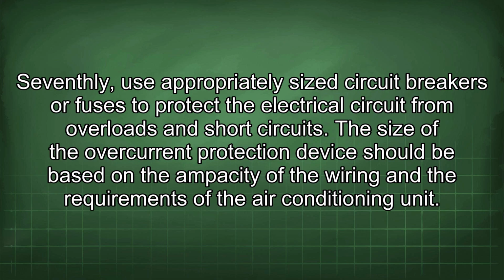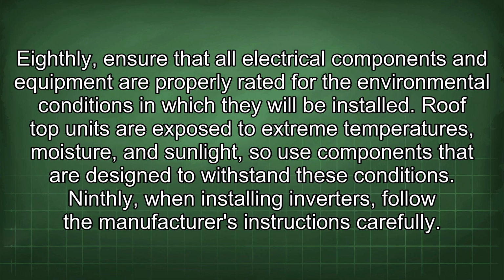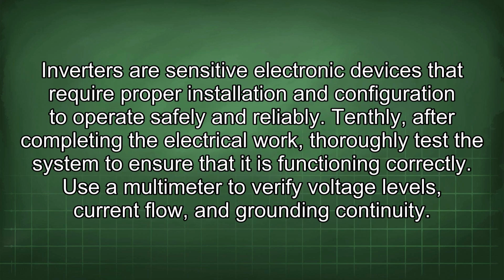Eighthly, ensure that all electrical components and equipment are properly rated for the environmental conditions in which they will be installed. Rooftop units are exposed to extreme temperatures, moisture, and sunlight, so use components that are designed to withstand these conditions. Ninthly, when installing inverters, follow the manufacturer's instructions carefully. Inverters are sensitive electronic devices that require proper installation and configuration to operate safely and reliably.